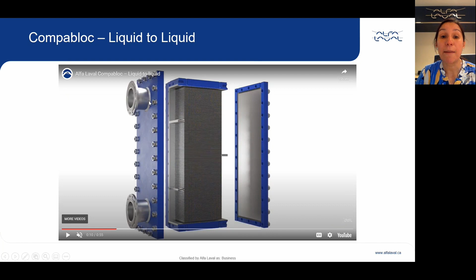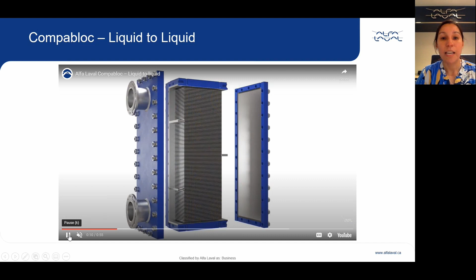Okay. So this is the Compabloc liquid-liquid configuration. And what you see here are pass plates. Now these pass plates are dividing the Compabloc plate pack into different sections. Each section behaves as a heat exchanger on its own. And now when the fluid comes in, it gets directed to pass multiple times through the same heat transfer area. That elongates the shape of the plate by making it a longer path through the heat exchanger. This longer path gives a longer residence time inside the heat exchanger and allows a closer temperature approach between the hot side and the cold side.